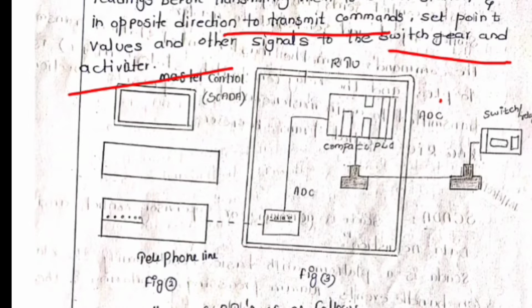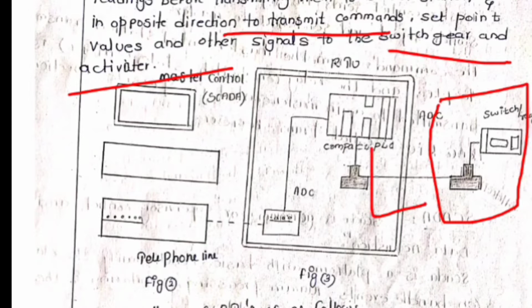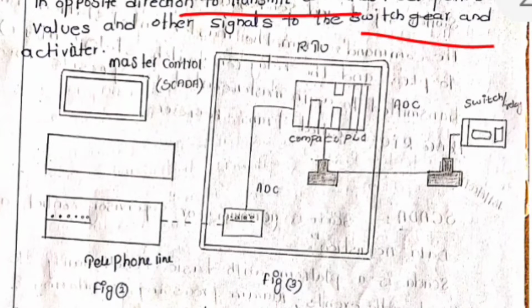It senses the various parameters by using switches, relays and protection devices like differential protection and many other protection devices. From those it receives the data from the sensors, and it is stored in the PLC, the programmable logic controller, which understands NO and NC contacts. Then the master control, that is SCADA, a control system, means a computer. From the RTU, it is interfaced to telephone lines or radio frequency lines. Wirelessly also we can transmit the data from the RTU. After that it goes to the master control.